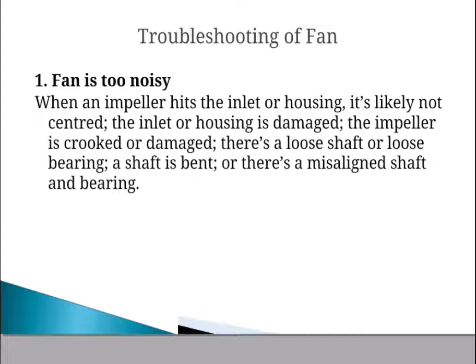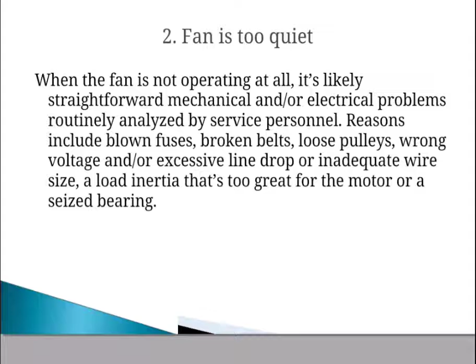Next one is the fan is too quiet. When the fan is not operating at all, it's likely a straightforward mechanical or electrical problem, routinely analyzed by service personnel. Reasons include a blown fuse, broken belt, loose pulley, wrong voltage, excessive line drop, inadequate wire size, load inertia that is too great for the motor, or seized bearings. These are the different reasons why the fan is quiet. So we have to find the reason and clear it.